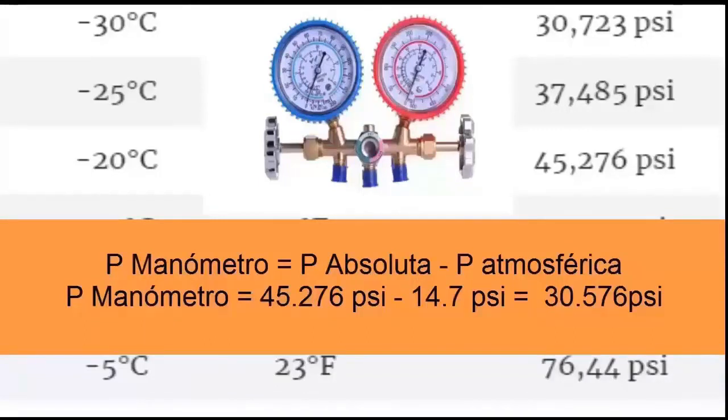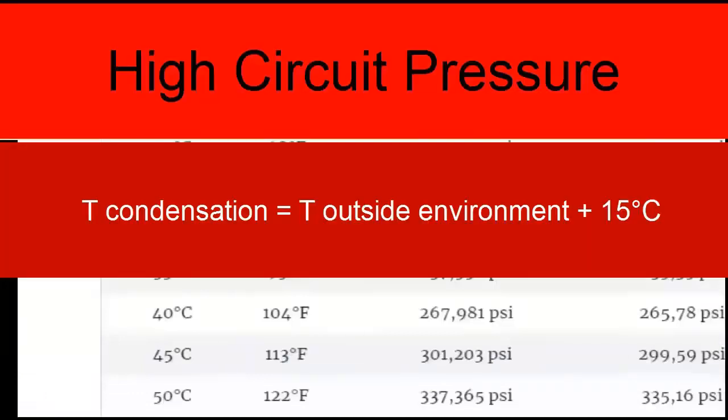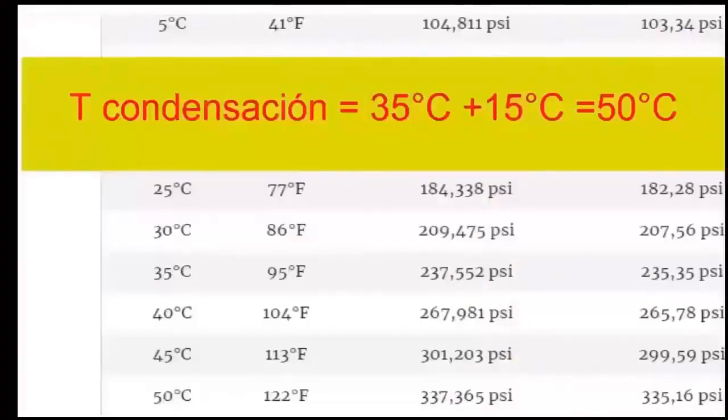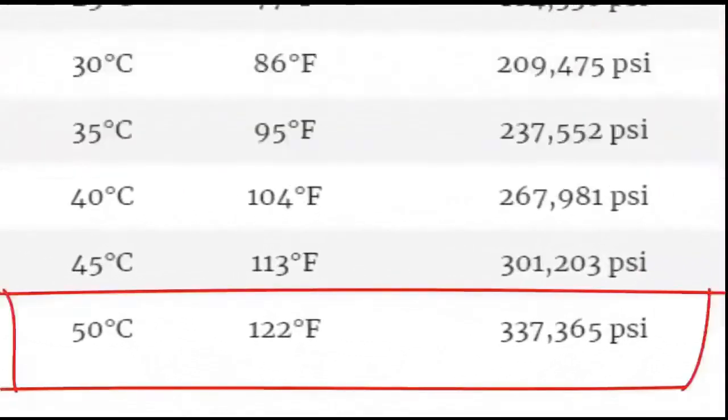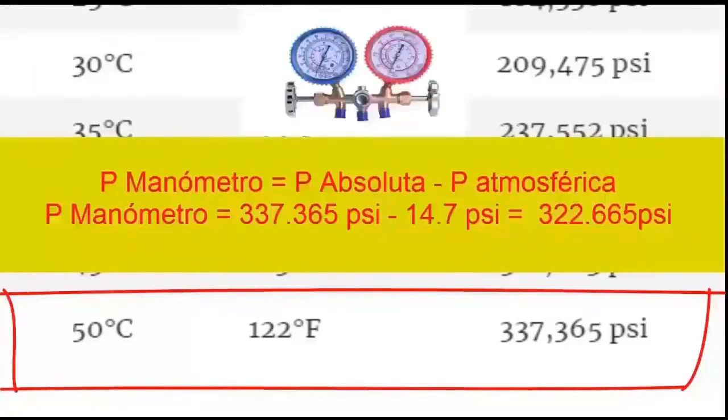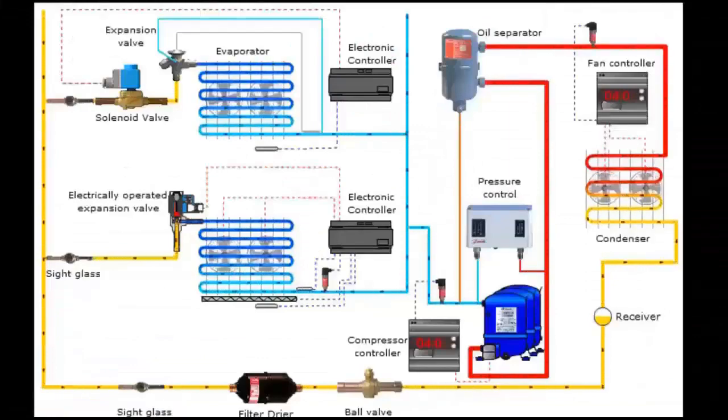To know the high pressure, simply use the ambient temperature increased by 15 degrees Celsius and look up the pressure value in the table. For an ambient temperature of 35 degrees Celsius, we increase 15 degrees to obtain a value of 50 degrees Celsius. Here is a 337.365 psi absolute pressure. To know the high or condenser pressure that the manometer would mark, we subtract the atmospheric pressure from the table value. 337.365 psi minus 14.7 psi is obtained, resulting in a gauge pressure value of 322.665 psi. Now let's see the parts of this cold room.